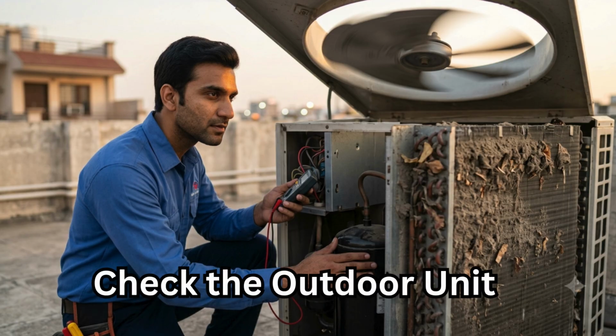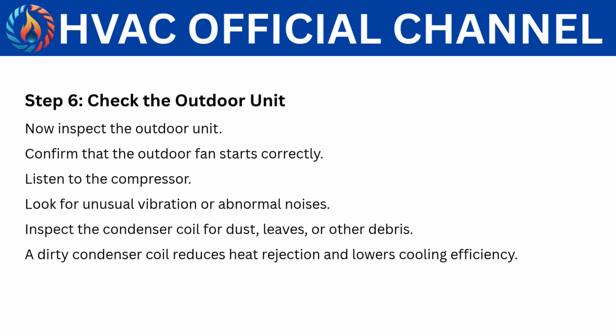Step 6. Check the outdoor unit. Now inspect the outdoor unit. Confirm that the outdoor fan starts correctly. Listen to the compressor. Look for unusual vibration or abnormal noises. Inspect the condenser coil for dust, leaves, or other debris. A dirty condenser coil reduces heat rejection and lowers cooling efficiency.